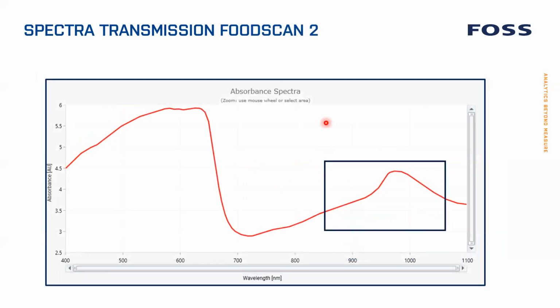And it's the same for a food scan. So this is a food scan 2. You see it's a little similar here. This is also the limitation of the instrument. It actually goes up all the way up to 6 absorbance units, and then it drops down when the sample becomes transparent. And this is using the same wavelength part from 850 to 1050. And the big peak here you see is water, because this is a meat sample, 70% of the meat is water. But again, they will all more or less look the same, all of the samples here.